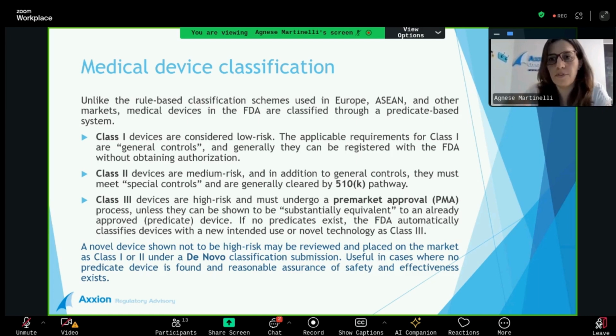This is the name of the type of procedure we must go through. And then we have class 3, which in general are high-risk devices, and they go through the pre-market approval, which is normally known as the PMA process. And this applies to cases where no substantially equivalent predicate device is found. And so it goes through a more complex process. Then we have something else that we would like to mention at this point: if a novel device is shown not to be a high-risk one, and can demonstrate reasonable assurance of safety and effectiveness, it can be reviewed and placed into the market as a class 1 or class 2 under a special submission, which is named de novo.